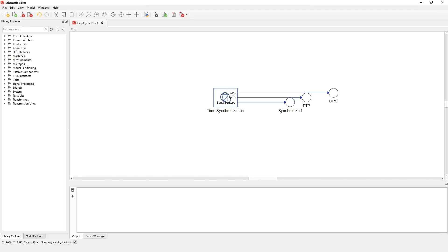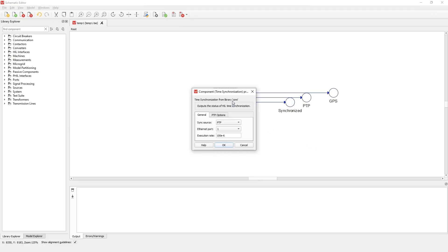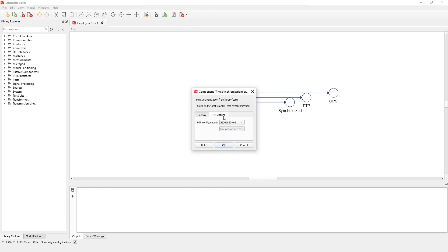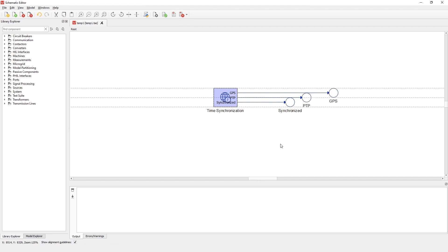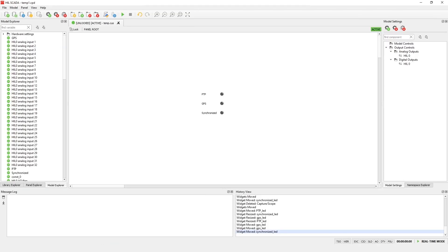Now, let's open schematic editor and configure the time synchronization component. Let's select the sync source as PTP and set the Ethernet port to 1. In the PTP options tab, we set the PTP configuration to IEC 61850-9-3. Now let's compile and run the simulation.